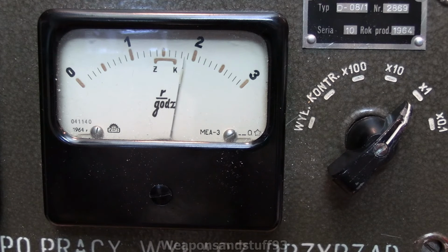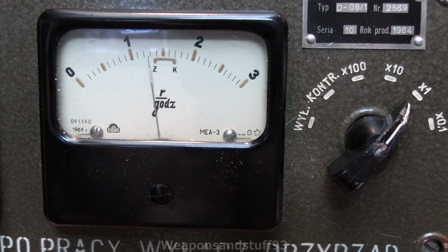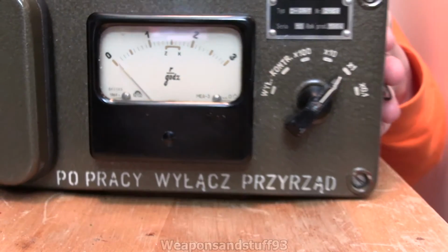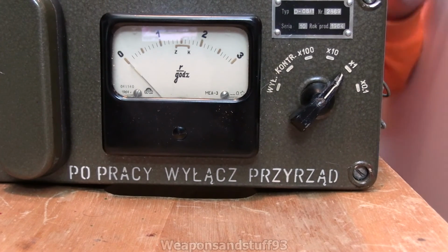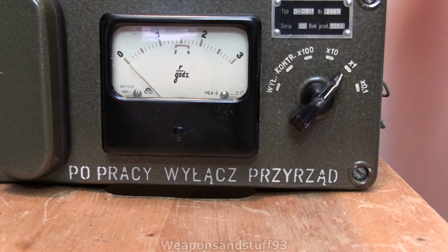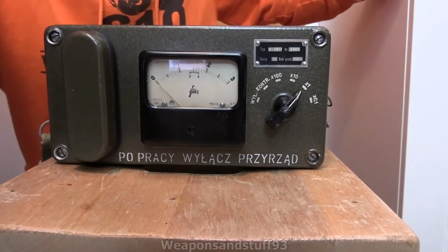Although you can see this chamber, the power calibration on it isn't quite right, because as you can see, it's jumping all over the place. Now, I know ionisation chambers do kind of do this. But yeah, what I'm going to do is just pull the sample out, and it should at least then go completely down to 0. Yeah, that's working. So cool. Hopefully this has demonstrated that these Polish D-08 meters, they're a bit old and clunky, as you can obviously see, but they do somewhat work.